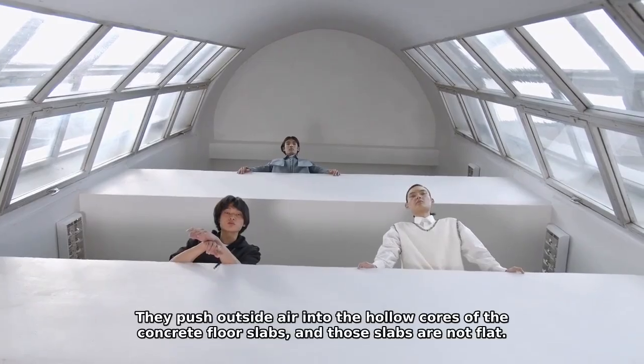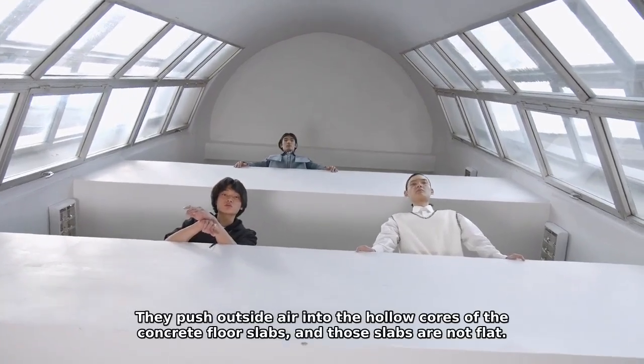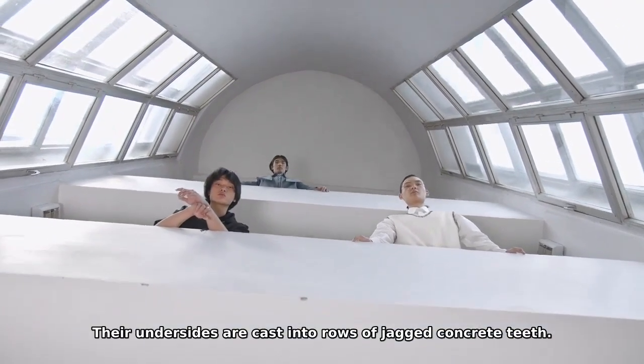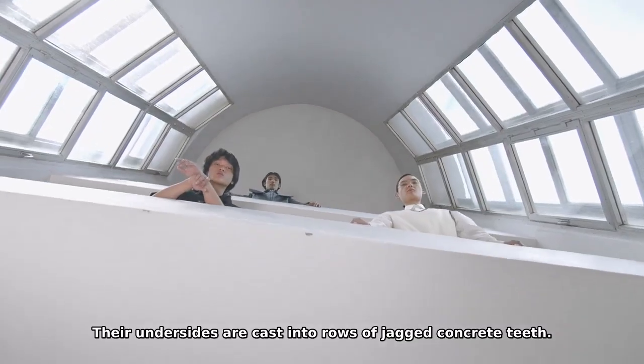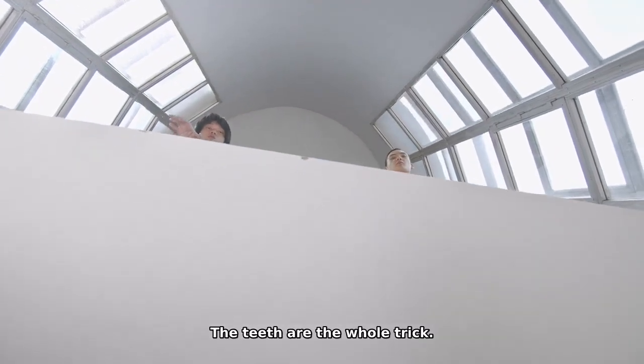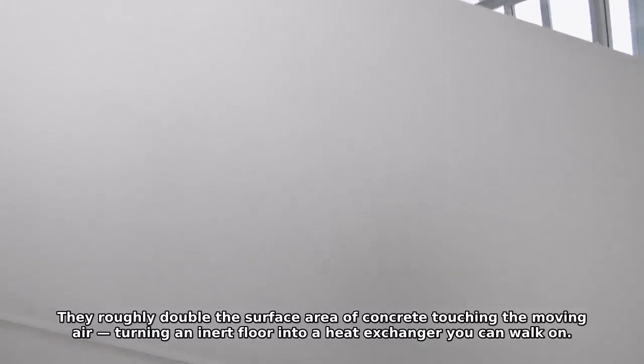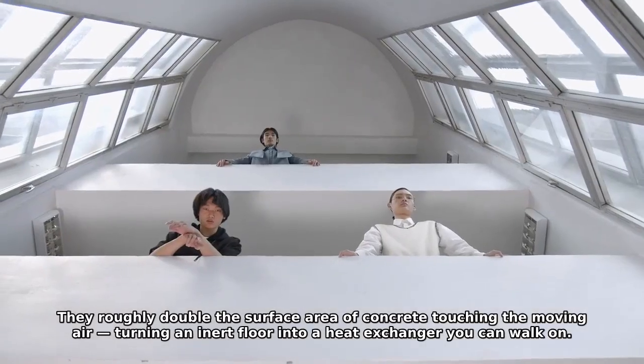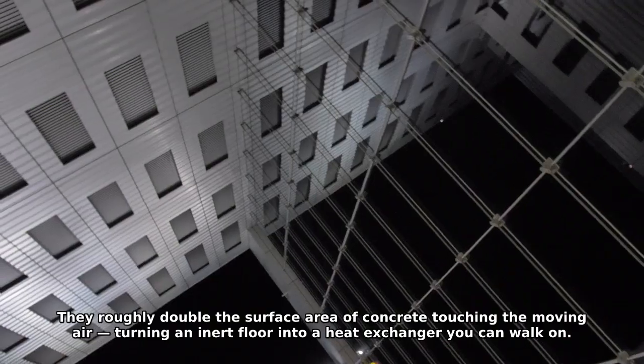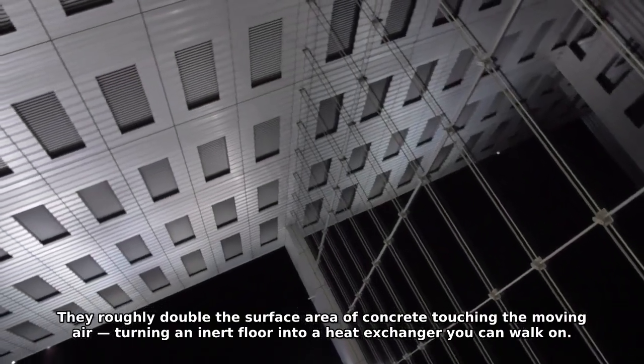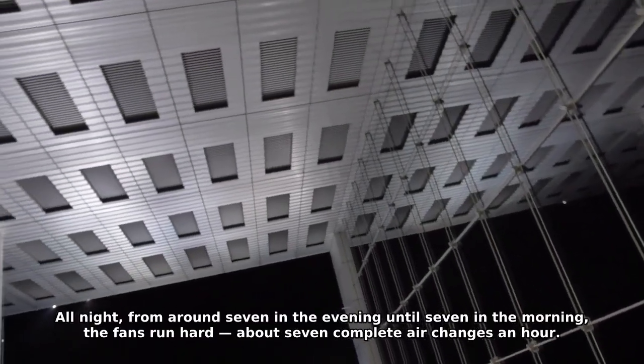They push outside air into the hollow cores of the concrete floor slabs, and those slabs are not flat. Their undersides are cast into rows of jagged concrete teeth. The teeth are the whole trick: they roughly double the surface area of concrete touching the moving air, turning an inert floor into a heat exchanger you can walk on. Here is the cycle.